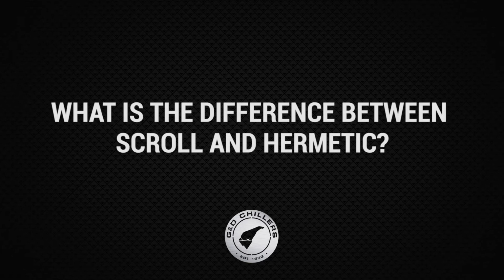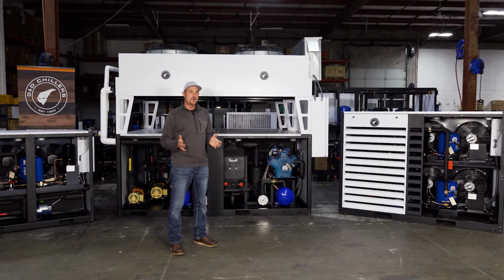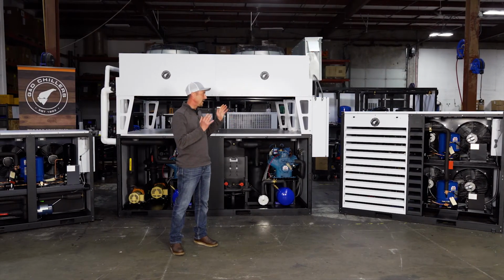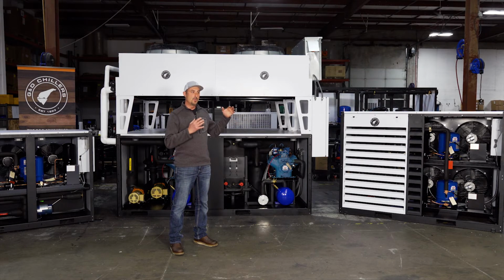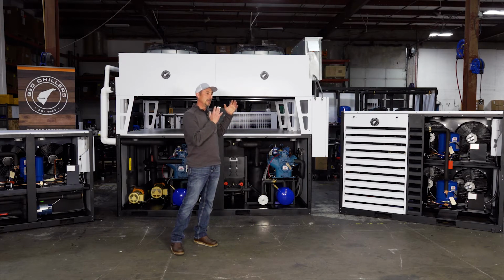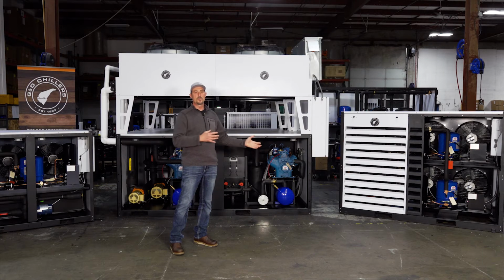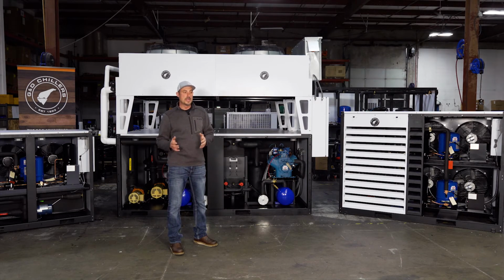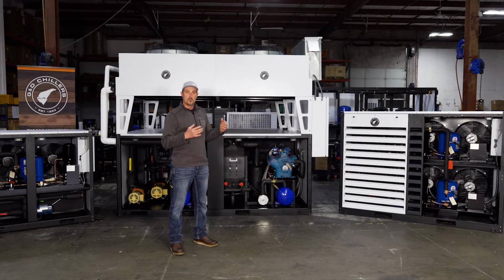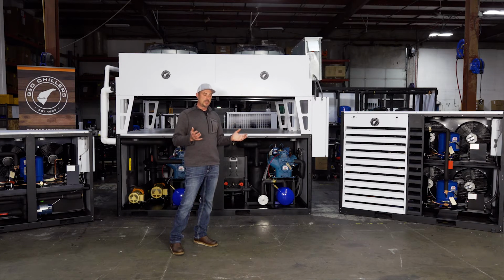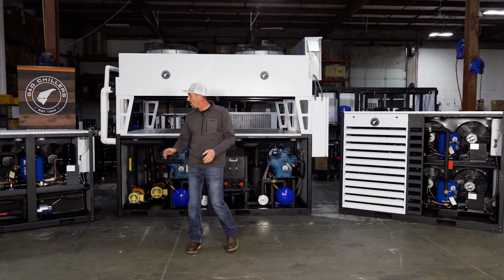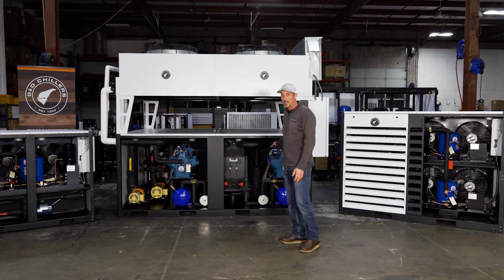One thing that comes up a lot in the brewing industry when it comes down to the actual chiller itself, and what makes something like a glycol chiller built for a brewery different from, say, an air conditioning chiller, is the compressor. The two main types of compressors that you'll see a lot of times within the chilling industry are a scroll compressor and a reciprocating compressor. All three of these chillers use reciprocating compressors.